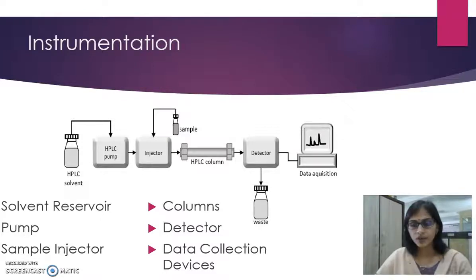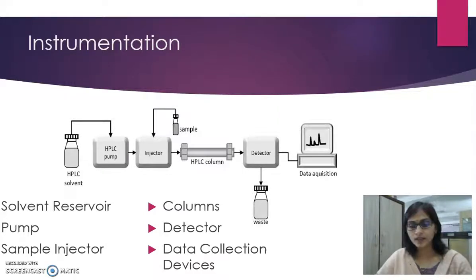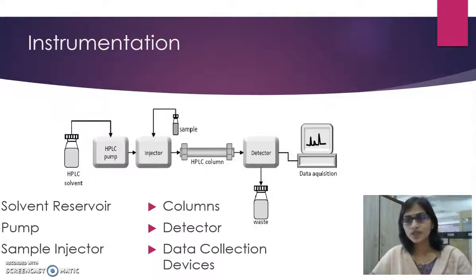During the chromatographic experiment, a pump can deliver a constant mobile phase composition, called isocratic, or an increasing mobile phase composition, called gradient elution. The sample injector can be a single injection or an automated injection system. Modern injectors are based on injection valves which allow the sample at atmospheric pressure to be transferred to the high pressure mobile phase immediately before the column inlet.